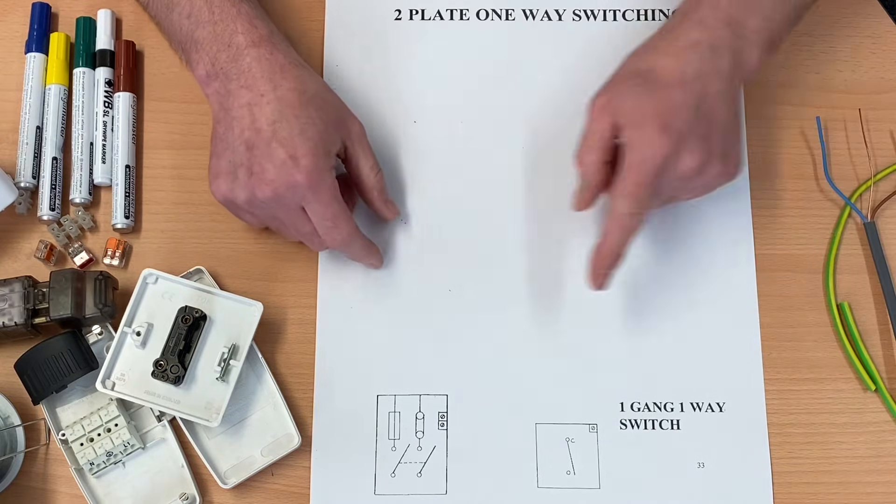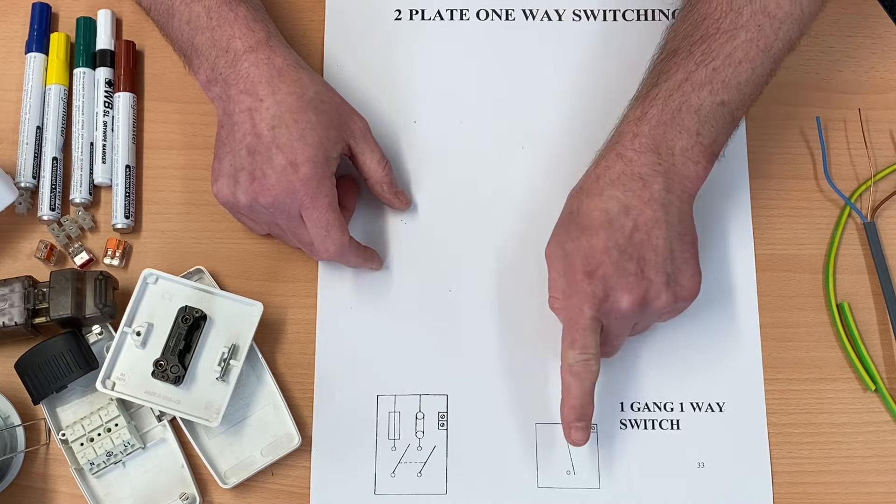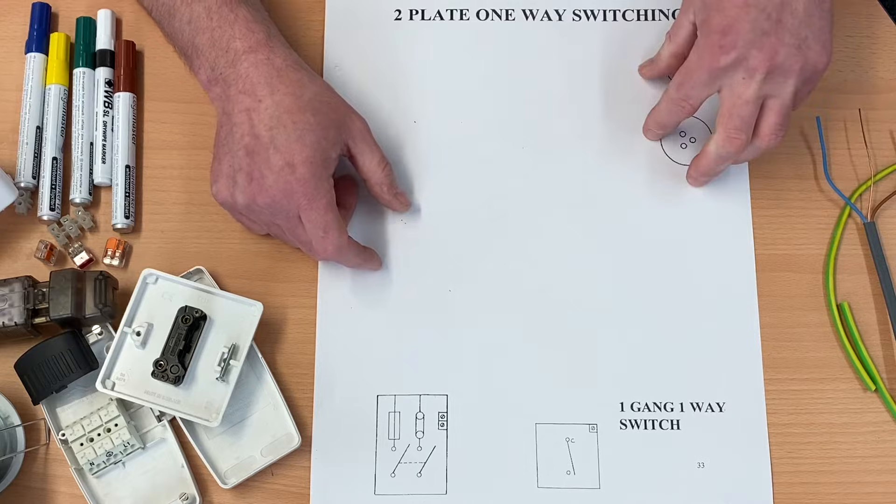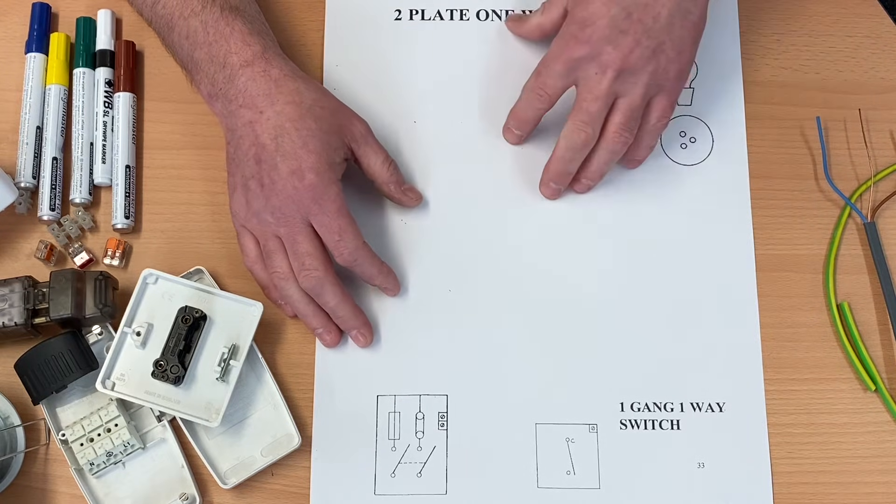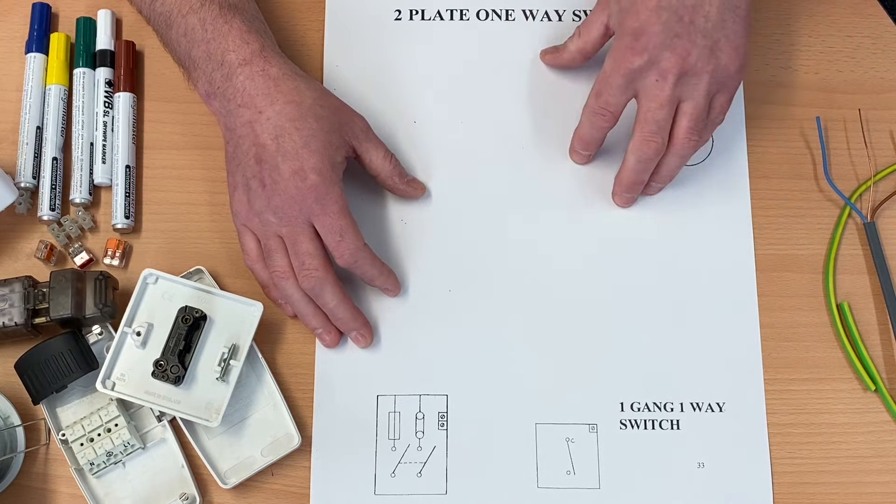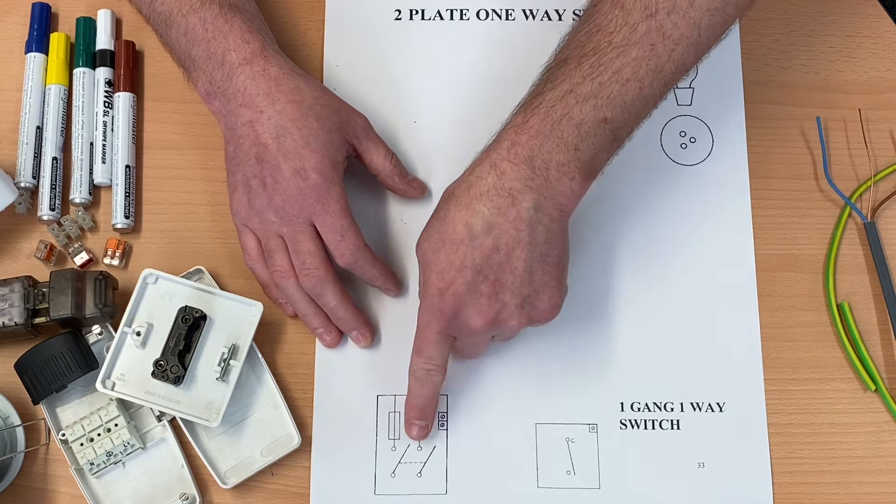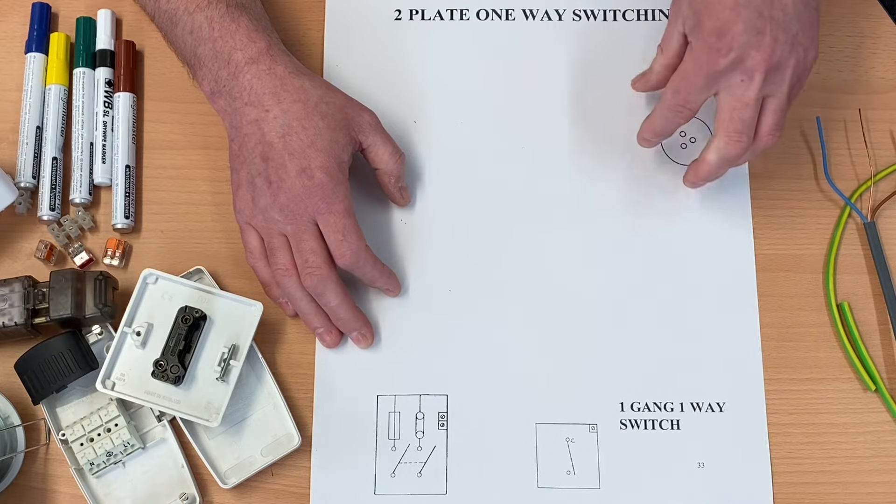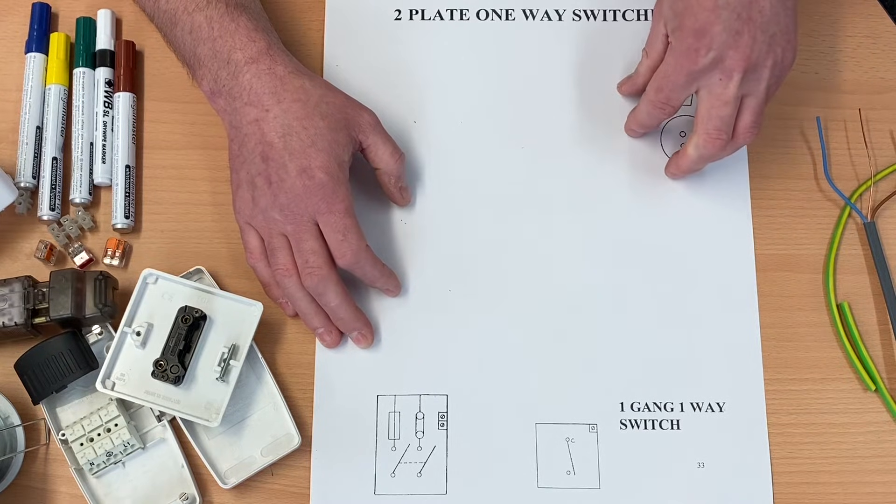So it's going to require us to take the supply in this case from the consumer unit directly to the switch, and then from the switch up to the lighting point itself. This is often used in industry, where there's loads of down lighters, say in a kitchen area. The electrician will bring the supply directly to the switch, and then from the switch to the lighting point itself, it cuts down the number of cables at the lighting point.